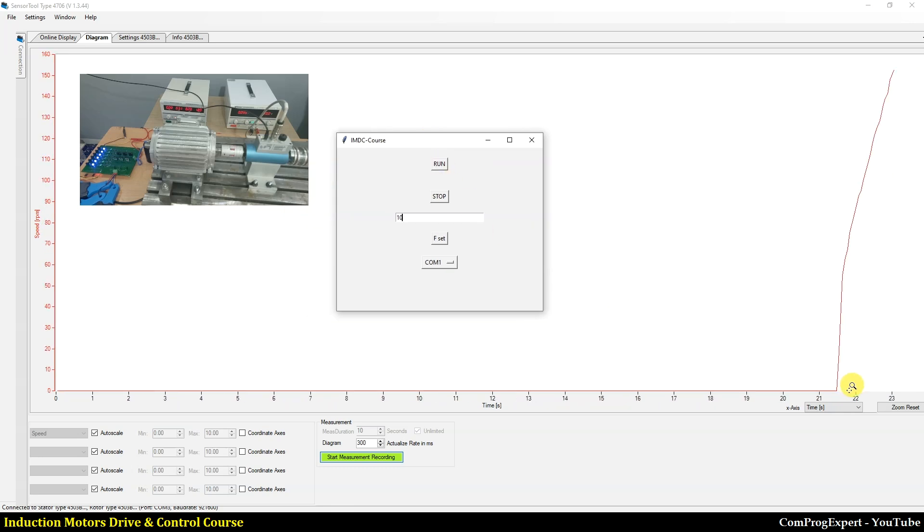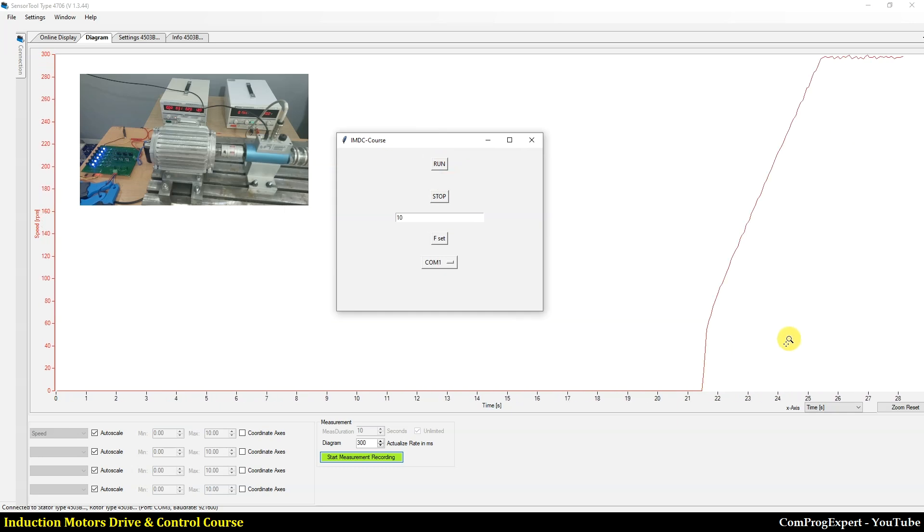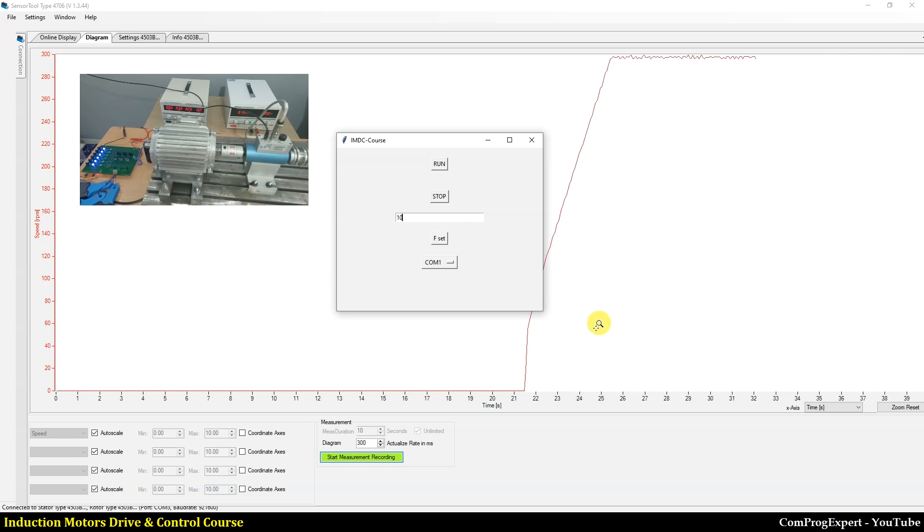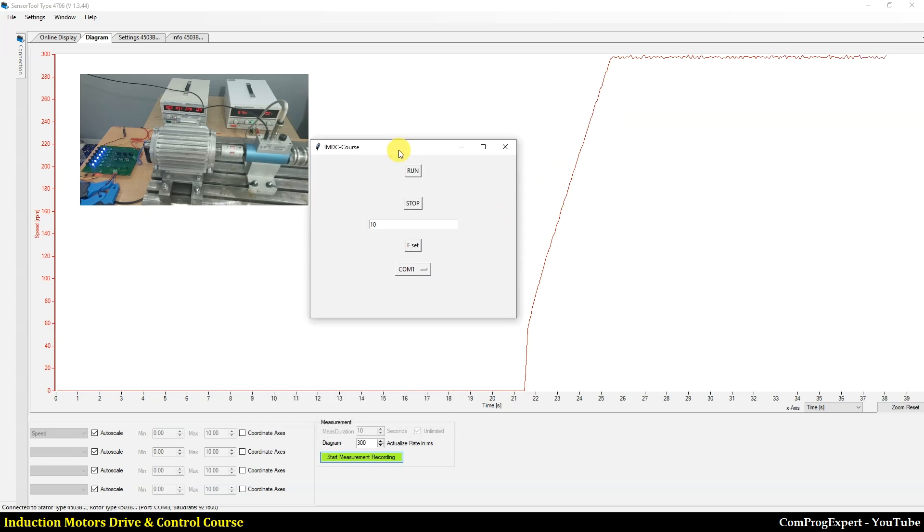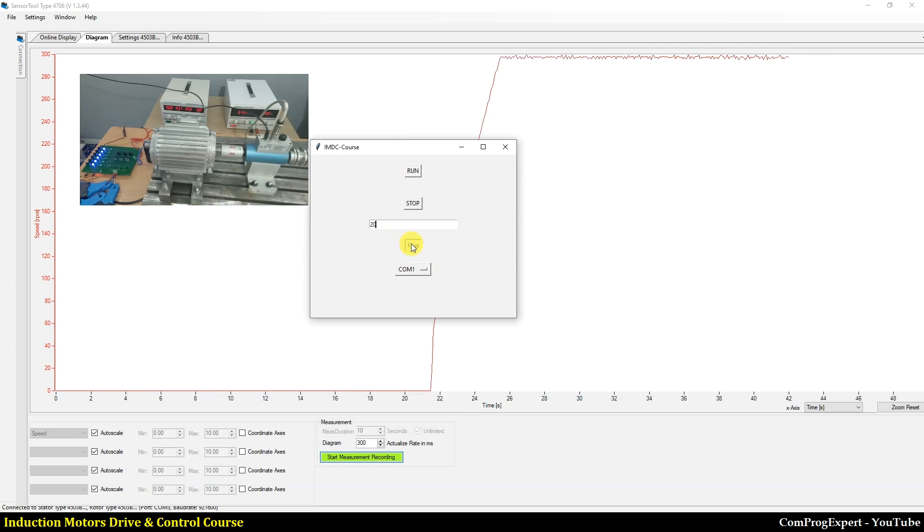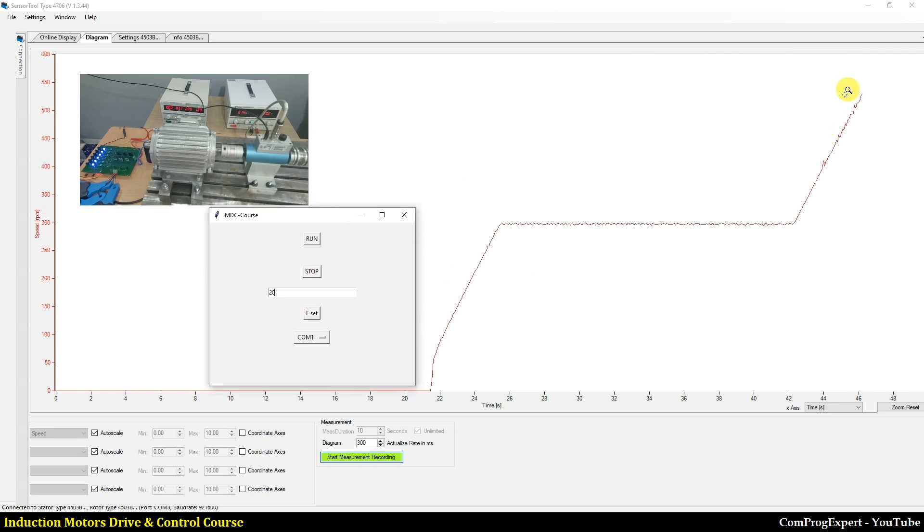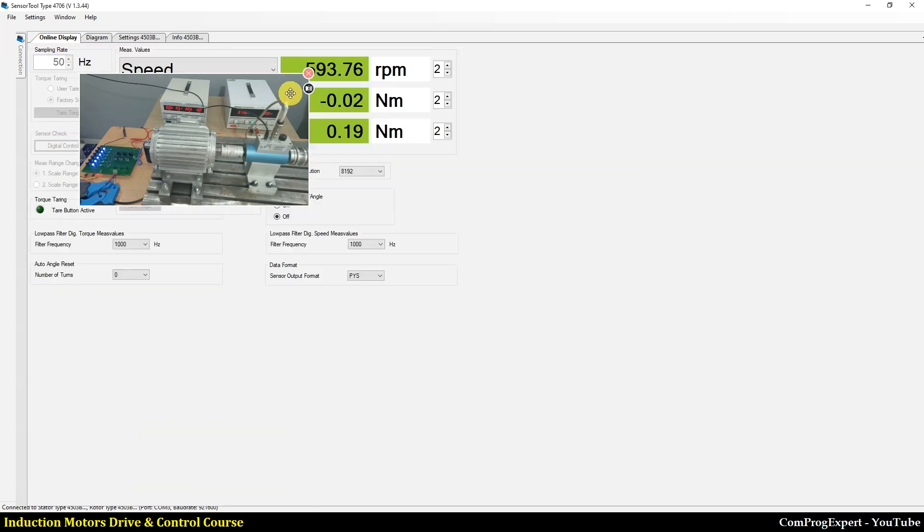So when the frequency is low, we apply that residual voltage. As you can see, we have this positive slope for increasing the frequency. So let's increase the frequency to 20. We have this rise in the motor speed. What is the value of the speed now? It's close to 600 RPM.